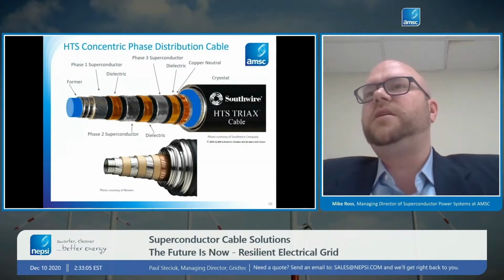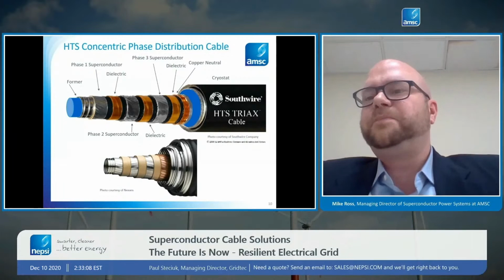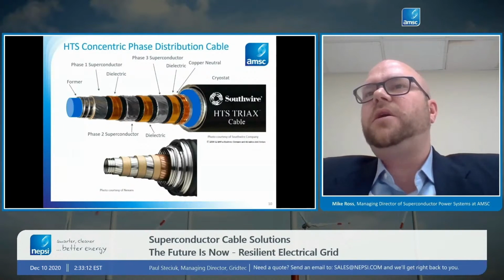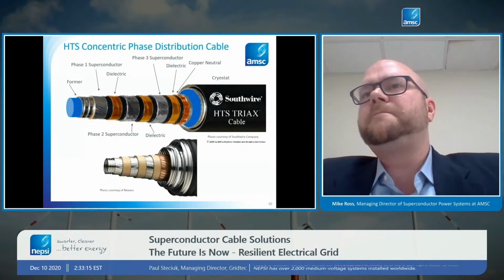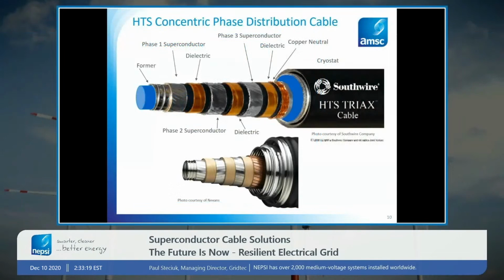This is the design. What you're looking at here is a three-phase cable, so phase A, B, and C are all concentrically wound in a single cable. This is very different than what you can do with copper. What that means is that you can have all three phases in a single cable, and each of those phases can be up to 4,000 amps. So almost up to 12,000 amps can be passed through this cable, or 4,000 amps three-phase. This single cable can replace up to 12. Remember, a conventional copper cable can only handle about 1,000 amps. So if you have 4,000 amps times three phases, that's 12 cables that are replaced by this one single cable.